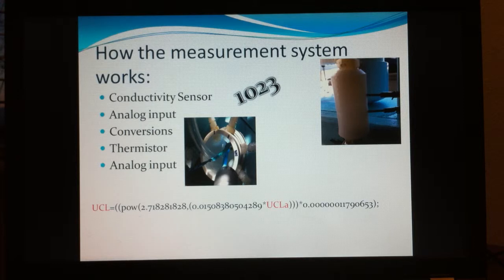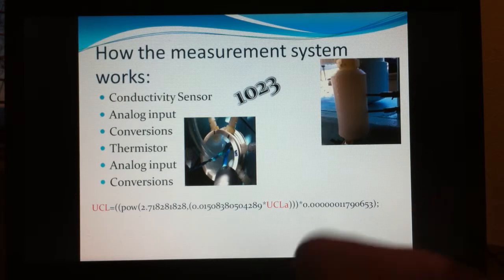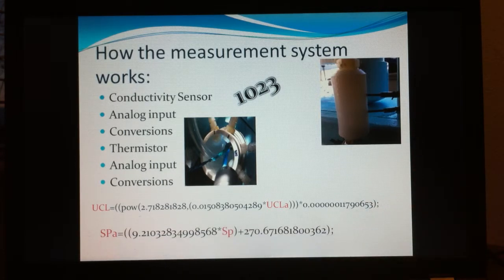The analog input has the same conversion factor, 1023, unlike an RTD, which would be much different because you're using 1.1 volts instead of 5. But for both the thermistor and conductivity sensor, you use 5 volts.